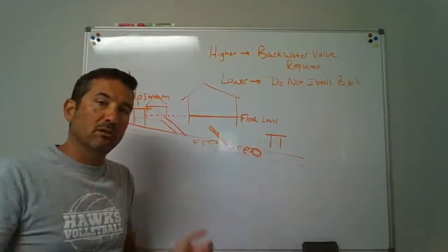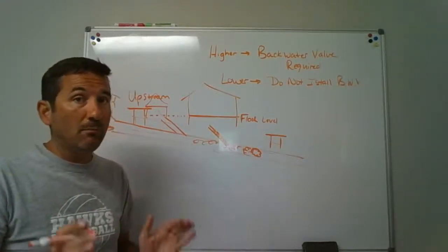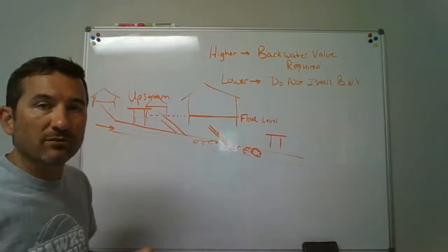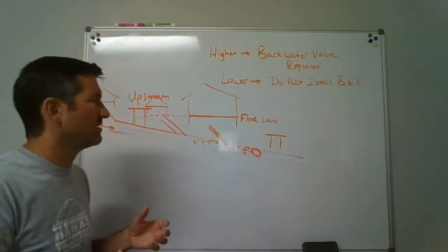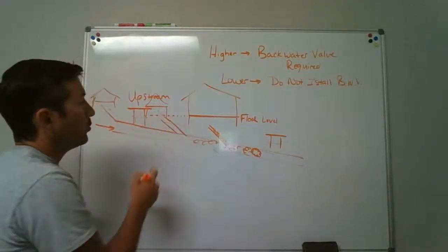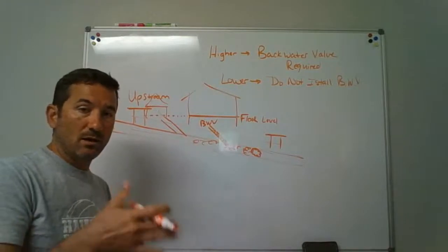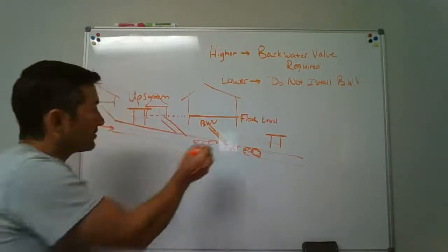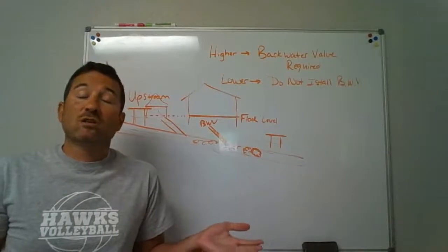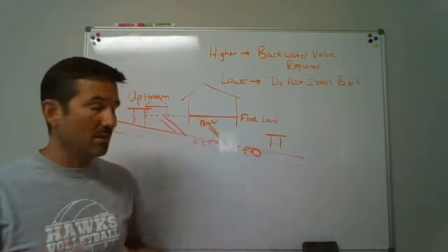It's just going to be bubbling up, and here it comes, and you're going to be like, I'm not using anything. I don't know, water's running, nothing, but stuff just keeps coming out my drains. Bad day, bad situation. So see what all your neighbors had for supper the night before when it's like, oh my goodness, this is disgusting. And it can make a huge, huge mess. So what we do is we would come in here. If you say, oh, we are lower than that, we install a backwater valve in the line, that check line, where everything drains through. And so if stuff starts backing up, that flapper is going to shut. I mean, you're stopped up. If you start using stuff, your stuff has nowhere to go. But at least it's keeping all of your neighbor's stuff from continuing to come out into your house.